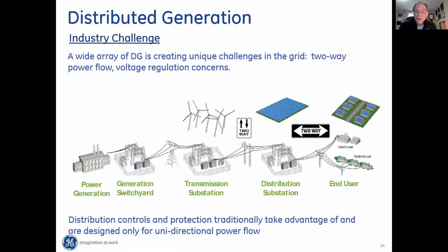We can integrate distributed generation at three different levels in the grid: transmission level, distribution level, and end user level. The distribution system's controls and protection were originally designed for electricity flowing in one direction only. Now, as we integrate distributed generation on the distribution system, we have two-way power flow, which creates some challenges.